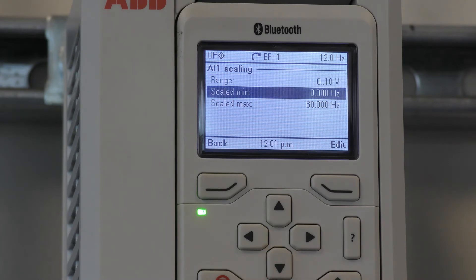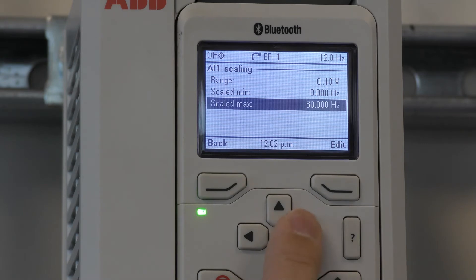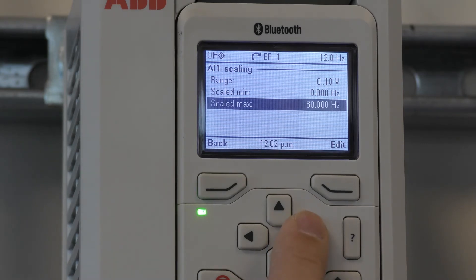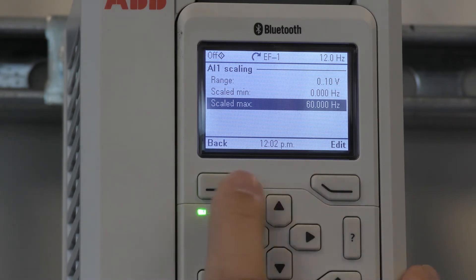We can also scale that 0 to 10 volt signal on the minimum and on the maximum. This is where you would change the max scaled frequency higher than 60 hertz if needed.